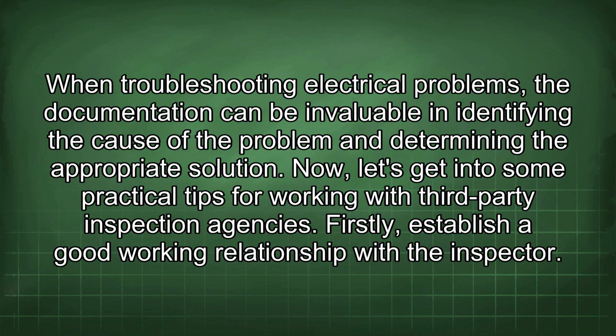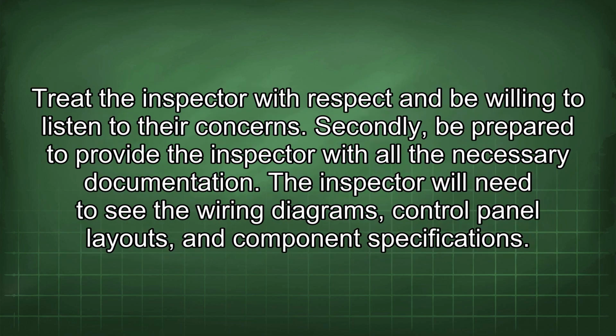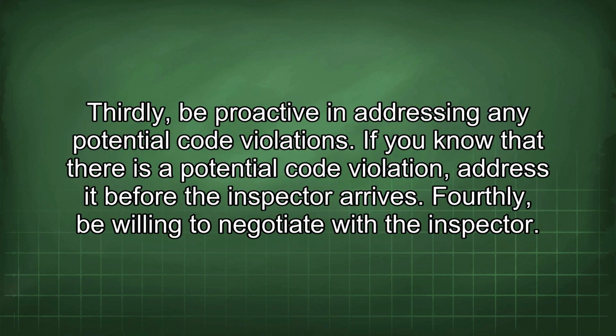Now, let's get into some practical tips for working with third-party inspection agencies. Firstly, establish a good working relationship with the inspector. Treat the inspector with respect and be willing to listen to their concerns. Secondly, be prepared to provide the inspector with all the necessary documentation. The inspector will need to see the wiring diagrams, control panel layouts, and component specifications. Thirdly, be proactive in addressing any potential code violations. If you know that there is a potential code violation, address it before the inspector arrives.